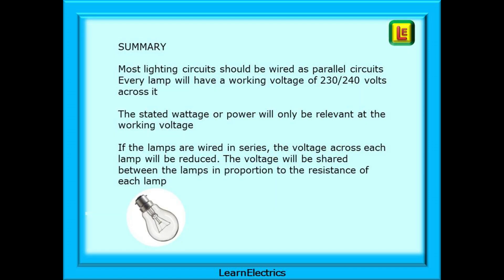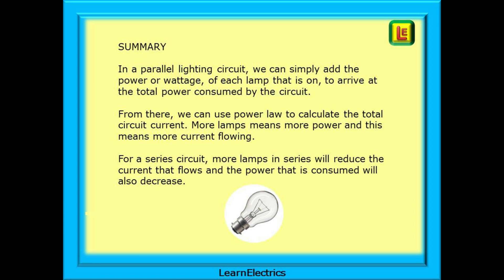In summary then, most lighting circuits should be wired as parallel circuits. Every lamp will have a working voltage of 230 or 240 volts across it. The stated wattage or power will only be relevant at the working voltage. However, if the lamps are wired in series, the voltage across each lamp will be reduced. The voltage will be shared between the lamps in proportion to the resistance of each lamp. In a parallel lighting circuit, we can simply add the power or wattage of each lamp that is on to arrive at the total power consumed by the circuit. From there, we can use power law to calculate the total circuit current. More lamps means more power, and this means more current flowing. But for a series circuit, more lamps in series will reduce the current that flows, and the power that is consumed will also decrease.